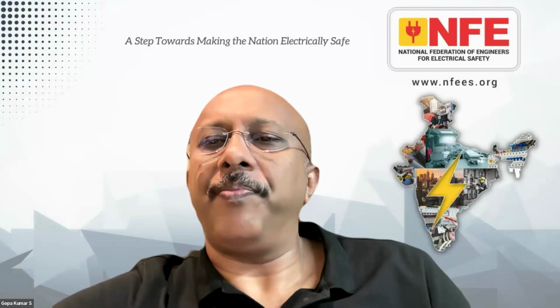Of course you need to consider it. There is a standard, IEC 60909 Part 0. It talks about the resistance of the cables and overhead lines, as well as the reactance of the cables and overhead lines. Absolutely. And then you need to break down the calculation into differing reference methods. For the overhead line, there will be one calculation; for the underground, there will be one calculation, and so on and so forth, because resistance is not dependent on installation reference method, but reactance differs according to the way it is installed.